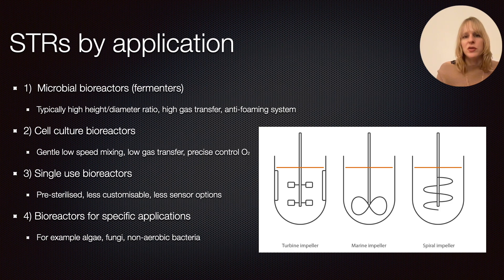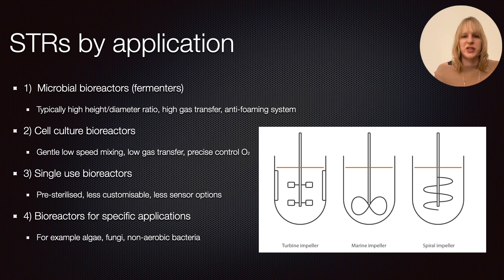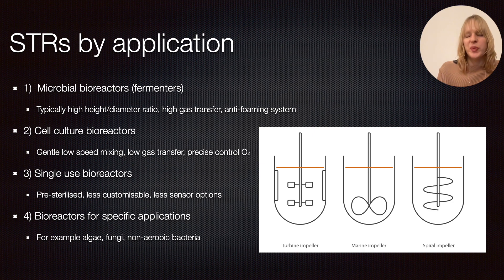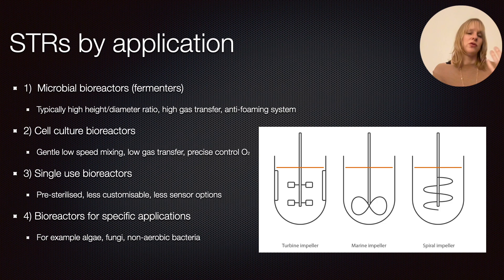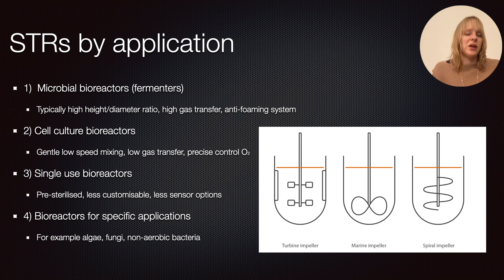For cell culture systems you need very precise control over oxygen because the cells are much more sensitive to it. You also control pH differently — mammalian cell culture systems are very sensitive to pH. Whereas a microbial bioreactor typically uses an acid-base feedback system, in cell culture it is much more common to use carbon dioxide to regulate pH.